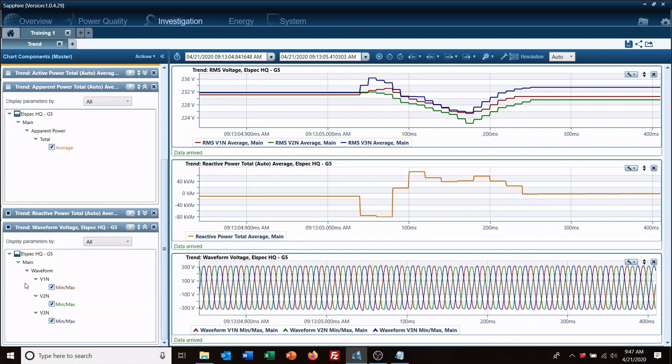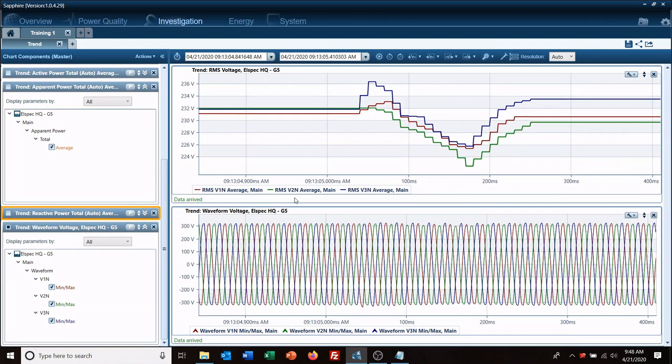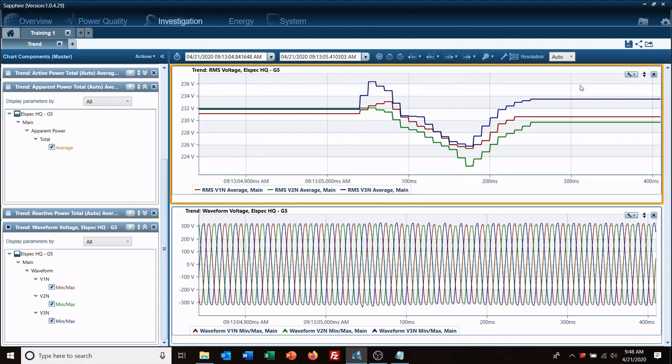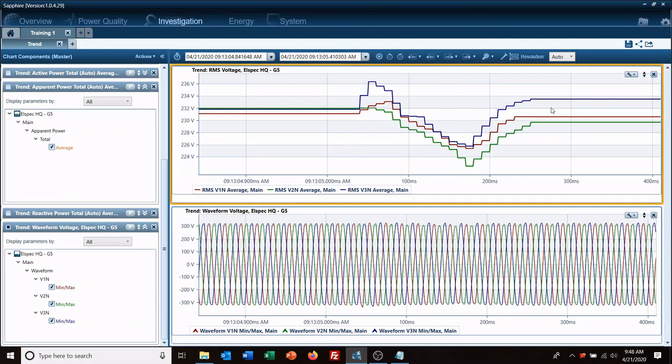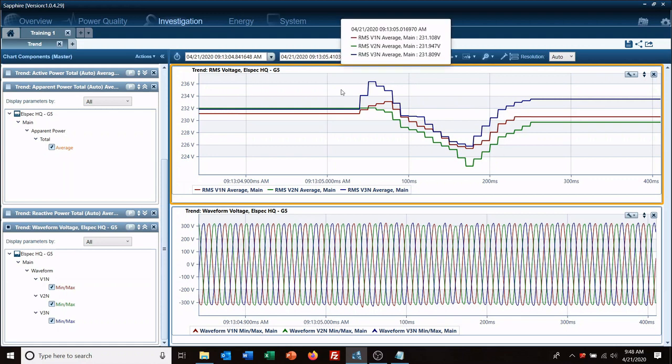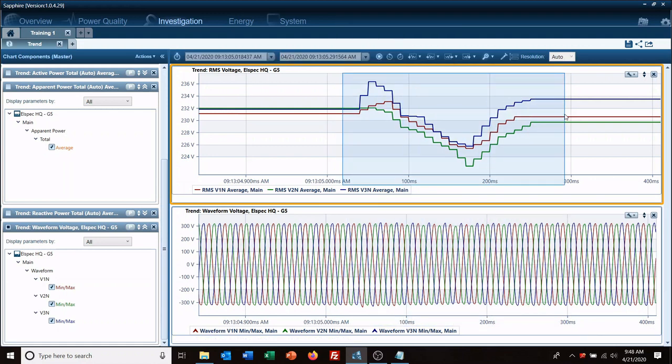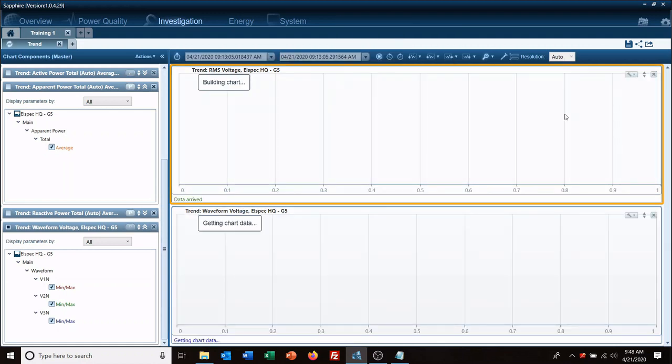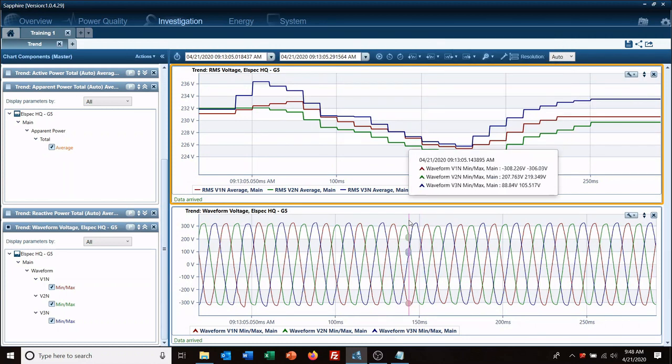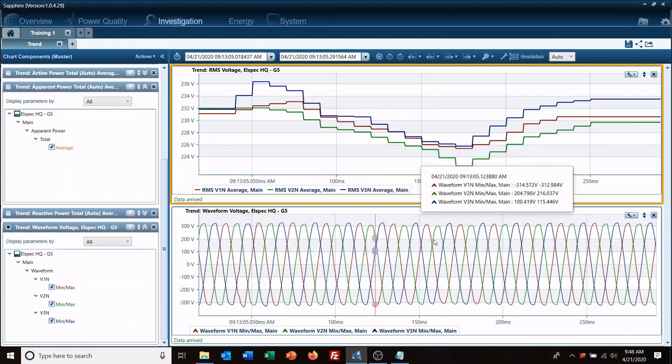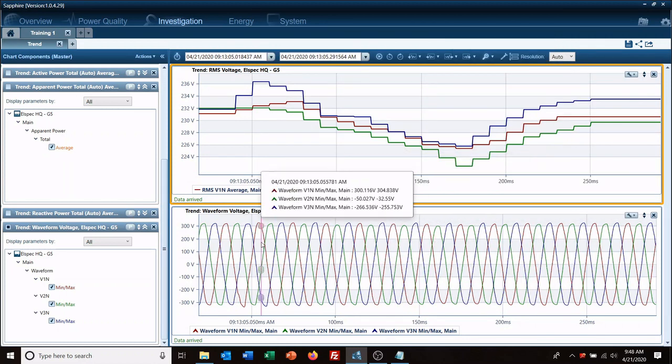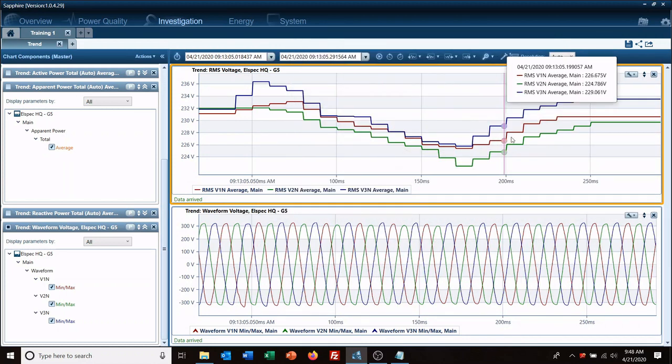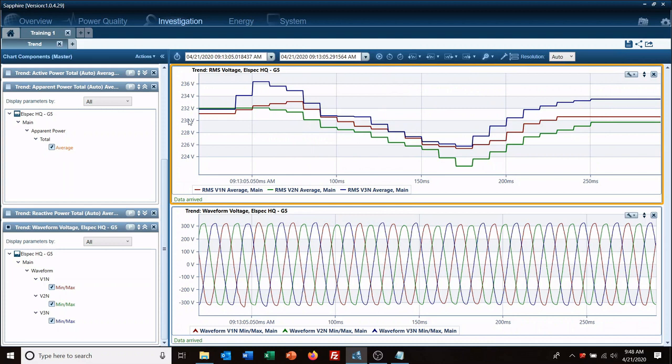And that allows us to zoom in. We'll go ahead and let's knock this power out of the way and the current out of the way. Let's see if this is actually anything of concern or if it's just a little bit. And you see it's just a little bit of voltage distortion, not even anything to worry about, but it allows you to zoom in and see what you have and what you're not looking at.